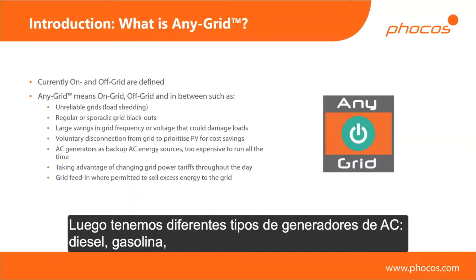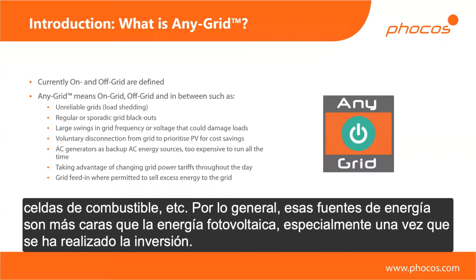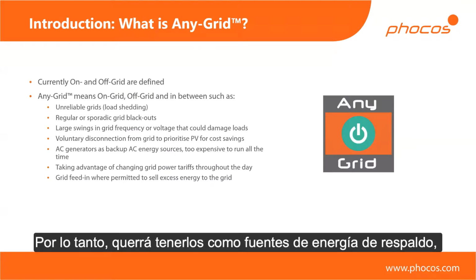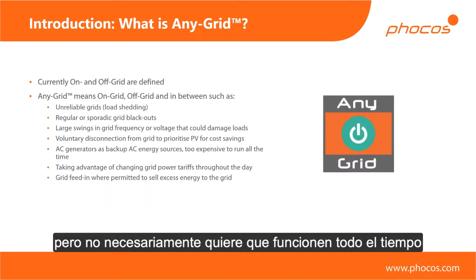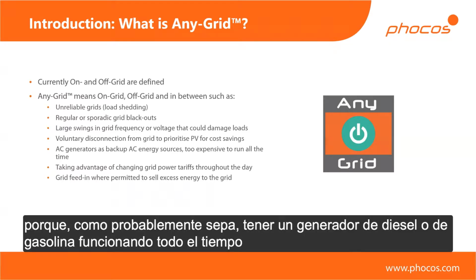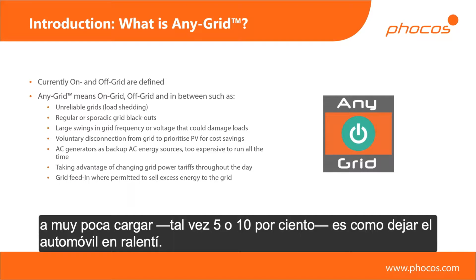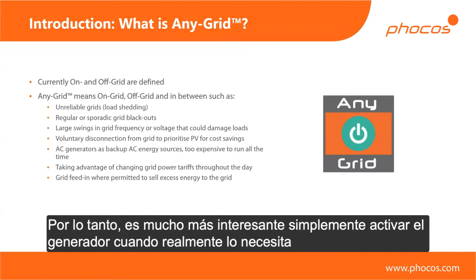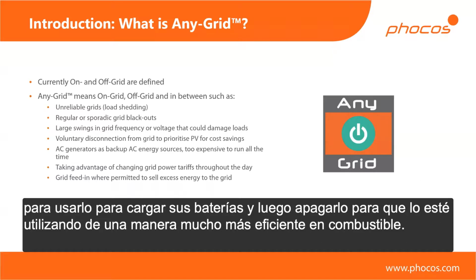Then we might have different types of AC generators. So this could be gensets of any kind, diesel, gasoline, could be a fuel cell, etc., where typically those energy sources are more expensive than PV, especially obviously once the investment has been made. So you want to have those as a backup energy source, but you don't necessarily want to have them running all the time. Because as you probably know, having a diesel or a gasoline generator running all the time at a very small load, like maybe at 5 or 10%, is like idling your car. You're basically just wasting fuel most of the time. So it's much more interesting to just activate the generator when you really need it, to then use that to charge your batteries, and then to switch it off again so that you're using it in a much more fuel-efficient way.